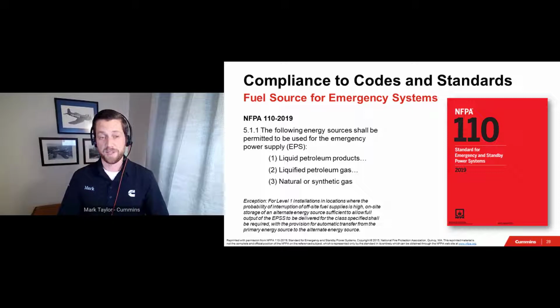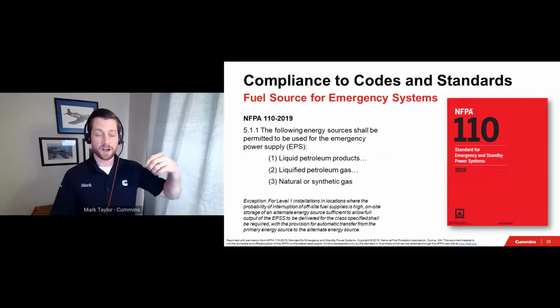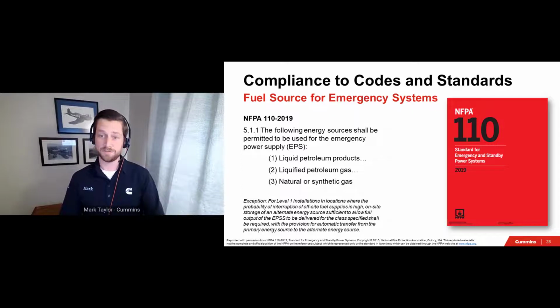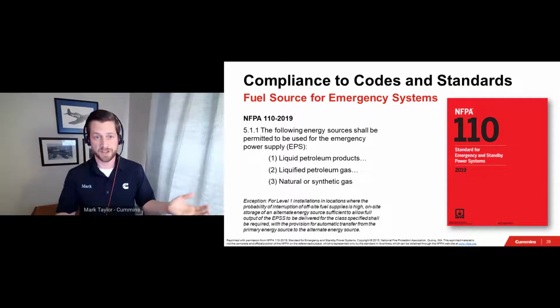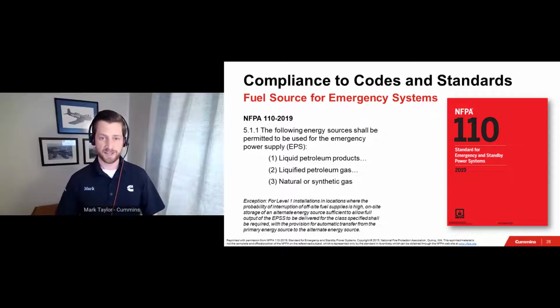The first thing I'll mention is that NFPA 110 does indicate that, where applicable, Level 1 emergency power supply systems may be fueled primarily from a natural gas utility source. This is to acknowledge that for many parts of the United States, the natural gas infrastructure is very reliable, to the point where the gas line can be the sole source of fuel. However, this exception text cites that in locations where the probability of interruption of that off-site fuel source is high, on-site storage of an energy source sufficient to allow for the full output of the EPSS to be delivered to the specified class in hours shall be provided. So the key operative word here is high. A high probability of gas utility interruption will drive the need for an on-site source of fuel.